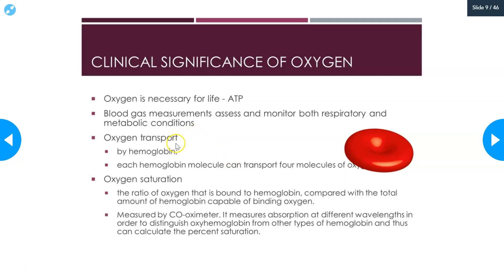Oxygen is transported in the blood by hemoglobin. Each hemoglobin molecule can transport four molecules of oxygen. The oxygen saturation is the ratio of oxygen bound to hemoglobin compared with the total amount of hemoglobin capable of binding oxygen. We rarely walk around with completely 100% saturation — it's quite normal to be 96%, 97%, or 98% saturation. It is usually measured by a co-oximeter, which measures absorption at different wavelengths to distinguish between oxyhemoglobin and other types of hemoglobin — deoxyhemoglobin, methemoglobin, sulfhemoglobin — and then calculates the percentage saturation.